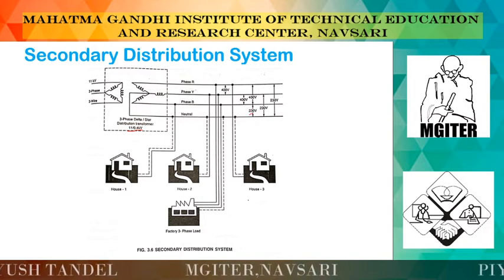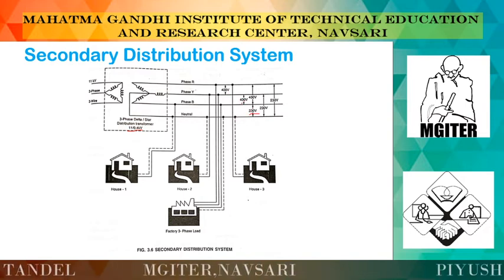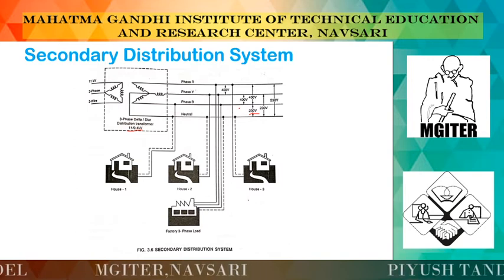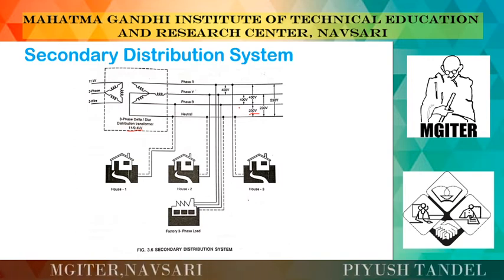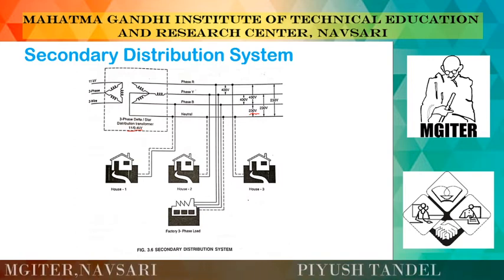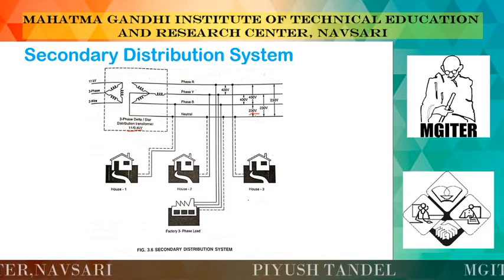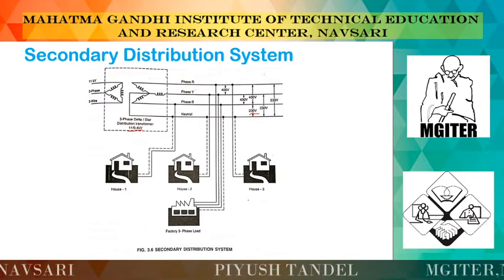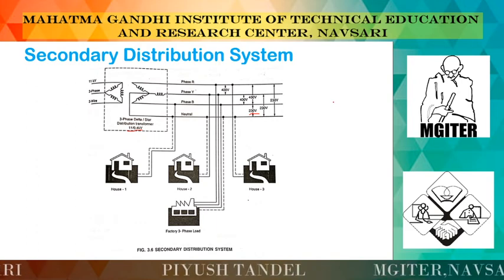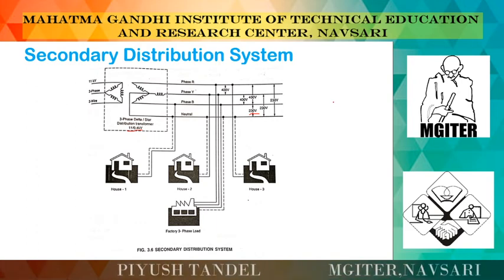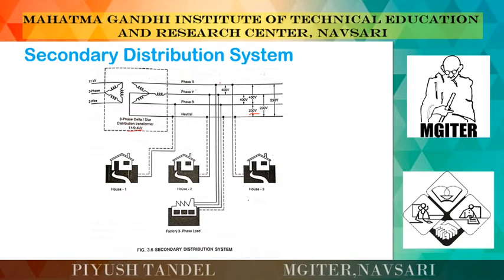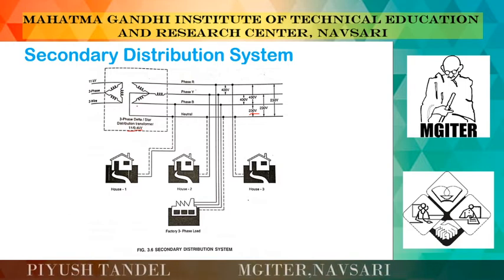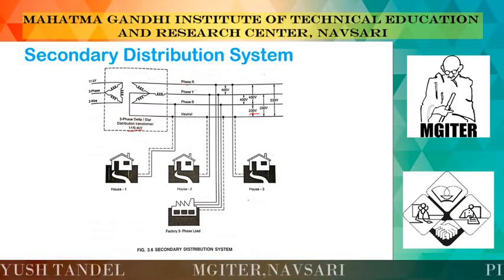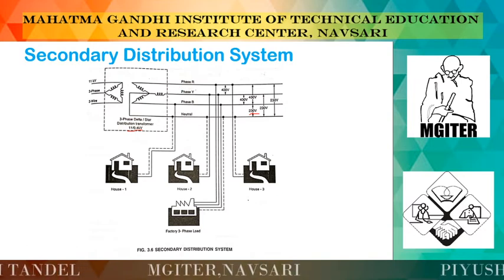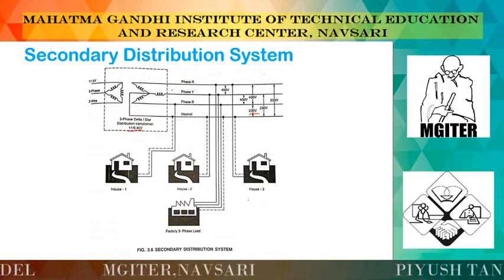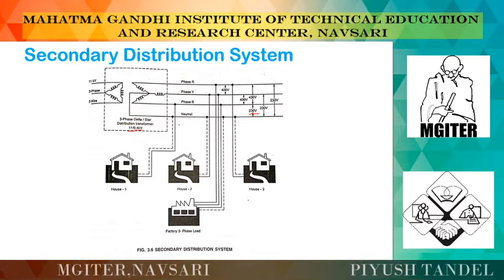Okay, between phase and neutral we can call it 230 volt, and between two phases we can call it 400 volt, and that is distributed directly to the consumers. Now this system is known as a low voltage or secondary distribution system. So from this portion we can call this a low voltage or secondary distribution system. And we can see that we have three wires on the primary side and four wires on the secondary side.